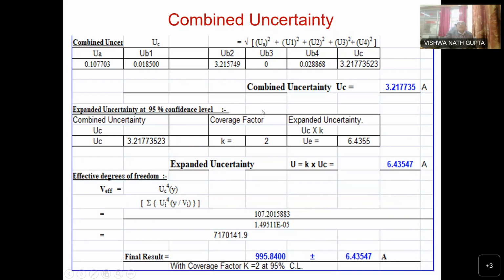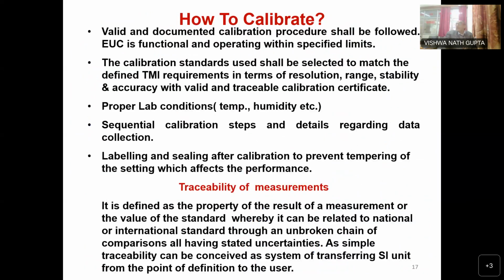In the column we are not writing this combined uncertainty. We are writing the expanded uncertainty at 95% confidence level, which is at 95.46 with coverage factor 2, which has to be multiplied by the combined uncertainty. That is why it is written approximately at 95%. As per the norms, we have to report the expanded uncertainty at 95% confidence level. So this is the final result for any measured output: the result after incorporating the error, plus or minus how much uncertain you are. This is one type of certificate for one parameter that we have shown here, sir.